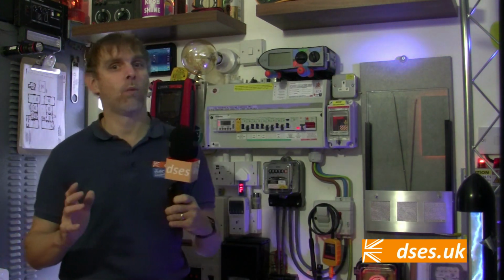Now, the thing about wholly new installations is that if you're rewiring or installing a new electrical installation from scratch, then you're the one designing it, so you know what's where and how it all bolts together. Therefore, the inclusion of an ARC fault device ought not to cause you too much grief, other than financially, which I'll come to later. However, where we're plopping new consumer units onto existing wiring and attempting to apply ARC fault detection in domestic dwellings that previous DIYers may have hacked away at, it might well see us struggling to keep the power on afterwards. I'll be looking at how you can mitigate against nuisance ARC trips later in this presentation.